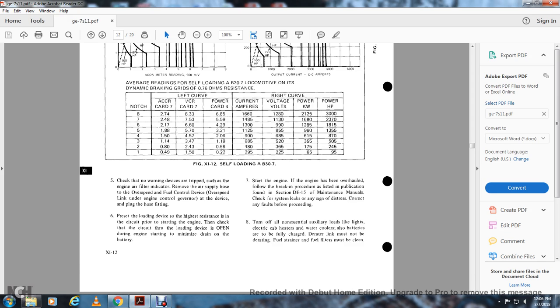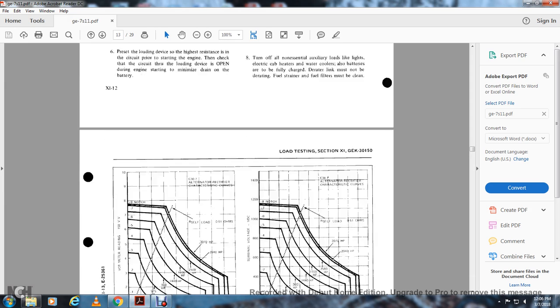8. Turn off all non-essential auxiliary loads like the lights, electrical cabin heaters, and water coolers, and also the battery must be fully charged. The derate link must not be in the derating position. Fuel strainers and fuel filters must be clean.